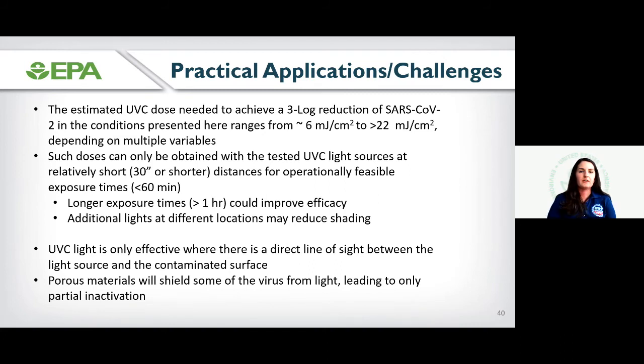So here in the conditions that we tested, we saw that the UVC dose needed to achieve the 99.9% or 3 log inactivation of SARS-CoV-2 spanned across a fairly large range, from about 6 millijoules per centimeter squared to greater than 22 millijoules per centimeter squared, depending on multiple variables. And again, that dose is as measured by our specific UVC 270C detector.